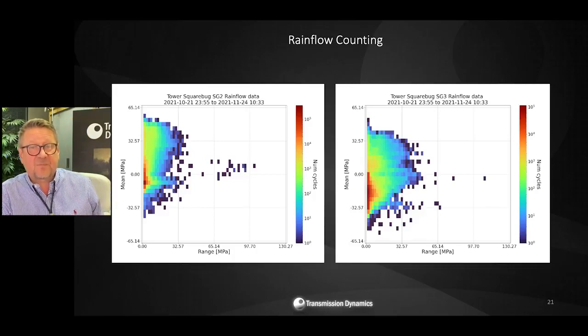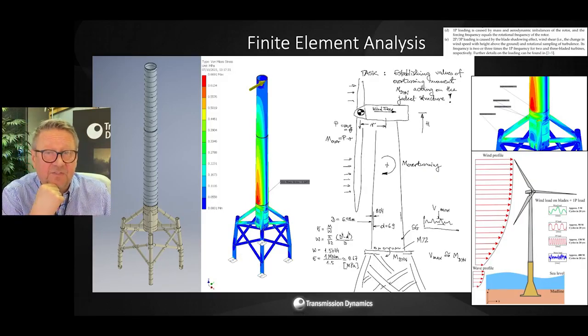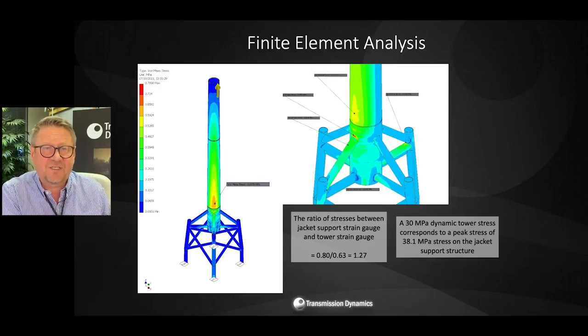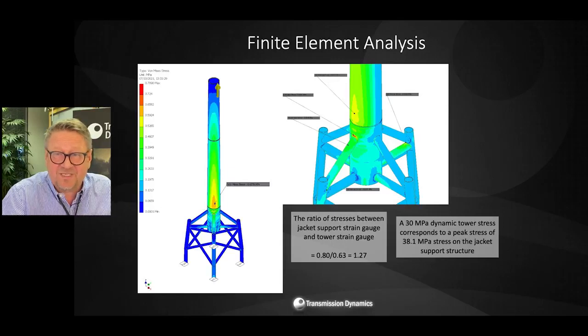Now, that data is then directly related to the combination of data analytics and finite element modeling. The finite element model of the wind turbine tower shown here allows us to do simple correlation between the values of strain measured, values of overturning moment as shown here, and then correlate that with the positions of the highest stresses. We may see clearly the highest stress levels not necessarily at the points where we deployed our sensors, but that's where finite element methods and modeling kick in as a powerful way of evaluating fatigue life cycles.